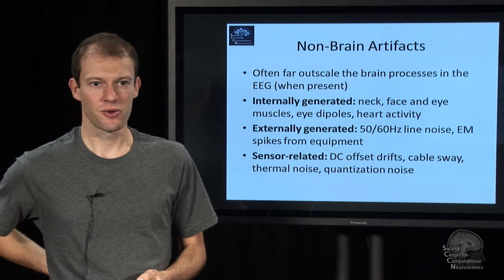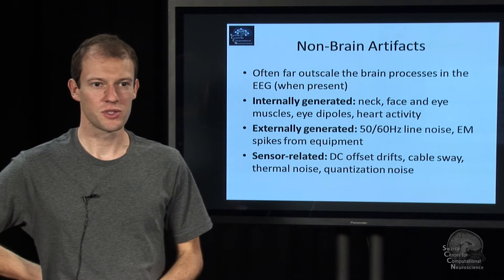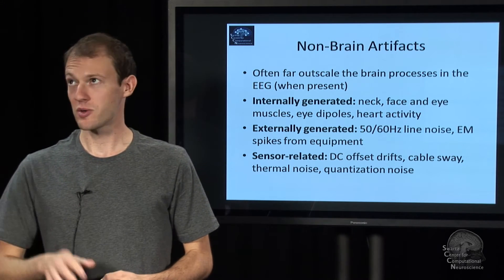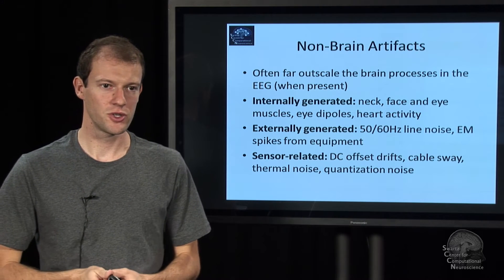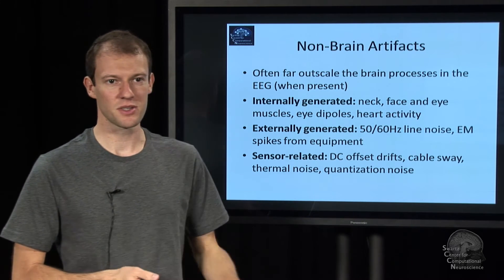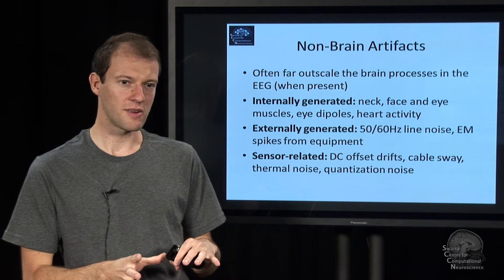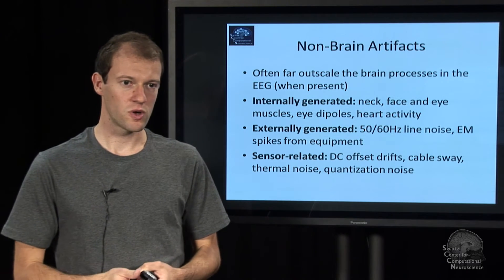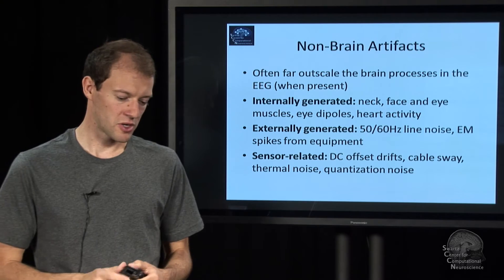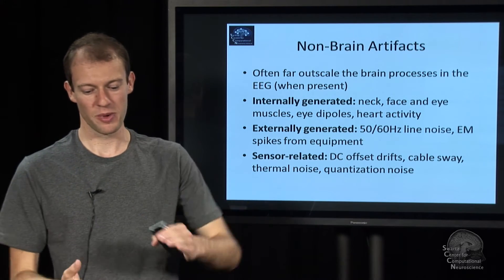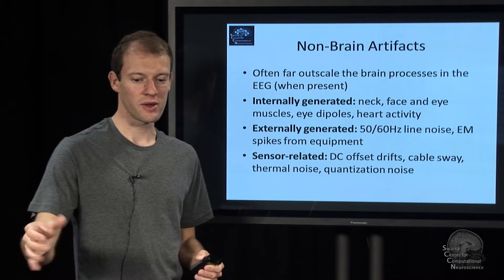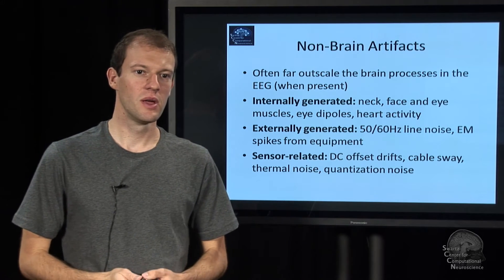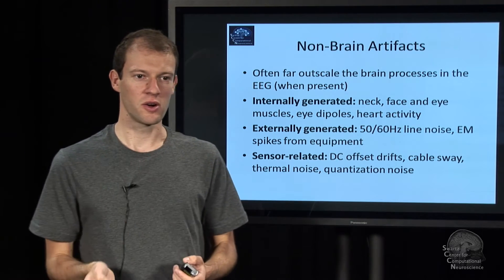Then there's externally generated artifacts like power line noise, EM spikes from fluorescent lights and things like that, which can mess up your signal. But in many cases these signals are simple enough that you can factor them out, because it's the same signal projected onto multiple electrodes — so if you observe it in one, you can subtract it from all the others if you know the weighting.